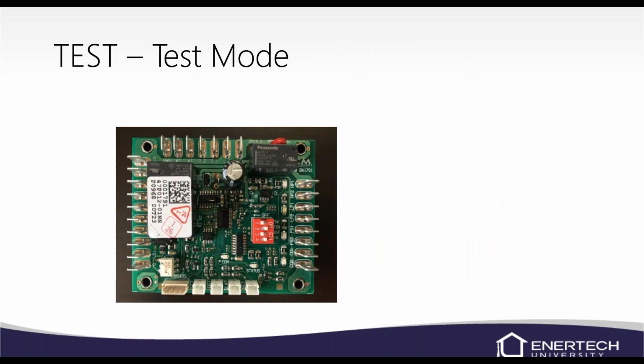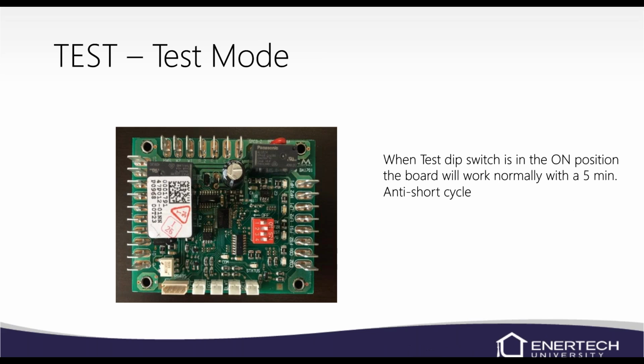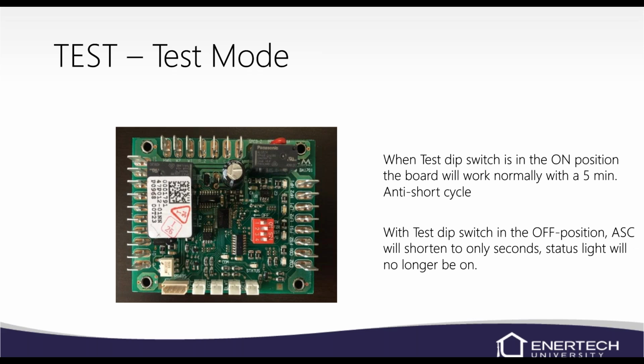So here I've shown this board with the red box in the middle. We have 4 dip switches: FSW, FZR, test, and O/U or O/V, depending. In test mode, if we put that to the on mode, which is how it comes from the factory, the board will work normally with your 5-minute anti-short cycle. If we flip that to the off position, your anti-short cycle will speed up to just a few seconds, and your status light in the bottom right corner of the lockout board will go out to let you know that you're in test mode. So you can test the unit and not have to worry about time delays.